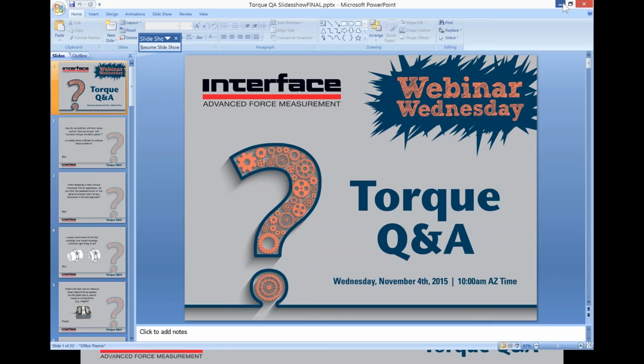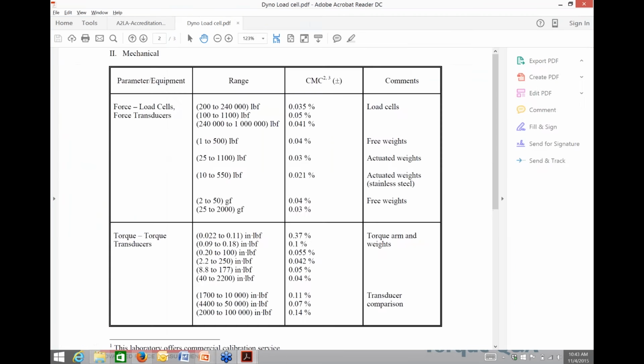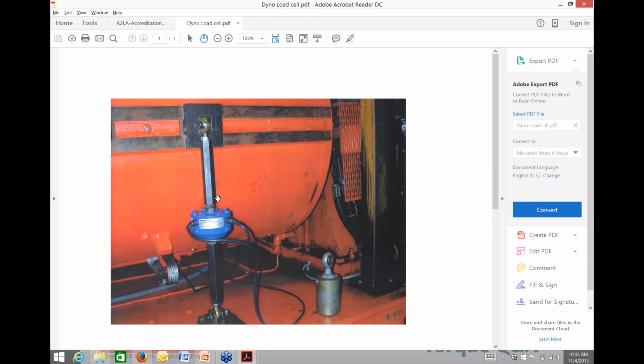Here we go. So this is a case of a dyno. Instead of using an inline torque sensor, it uses a load cell off center. And this is a great way to do it. This is an eddy current dynamometer, though, that is gimbaled at its center line, basically, to allow this. If it were, say, an AC motor bolted to a plate, it's very difficult to gimbal that system. So sometimes it's the geometry of the items involved in the test that really dictate whether you can use a load cell or you have to stick with a torque sensor.